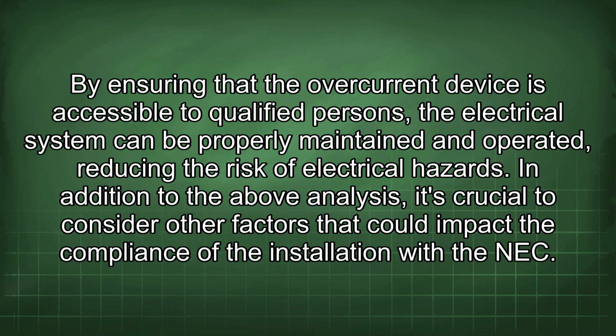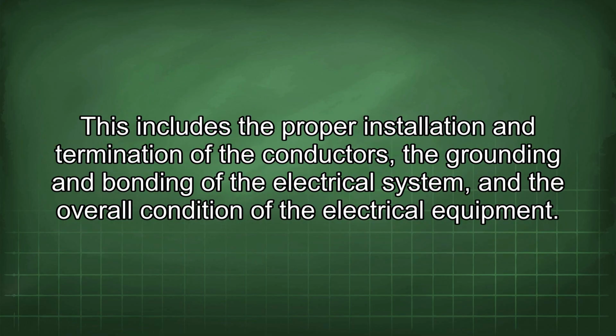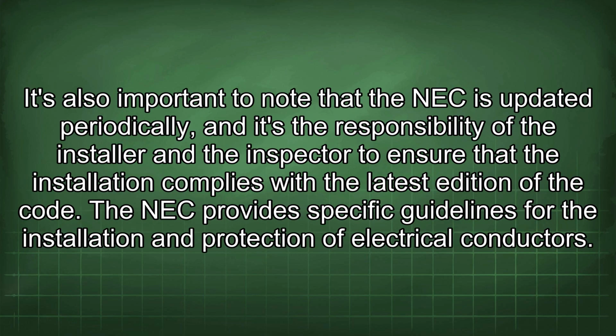In addition to the above analysis, it's crucial to consider other factors that could impact the compliance of the installation with the NEC. This includes the proper installation and termination of the conductors, the grounding and bonding of the electrical system, and the overall condition of the electrical equipment. It's also important to note that the NEC is updated periodically, and it's the responsibility of the installer and the inspector to ensure that the installation complies with the latest edition of the code.